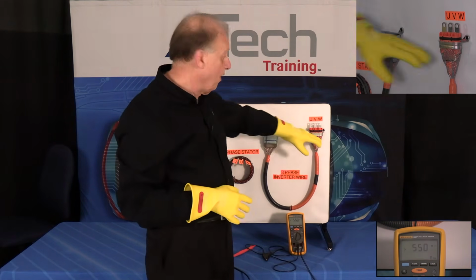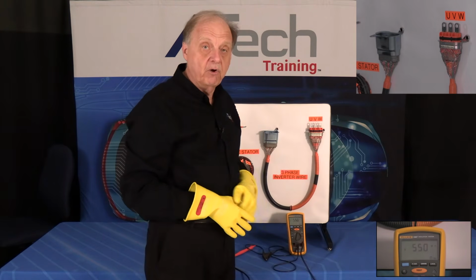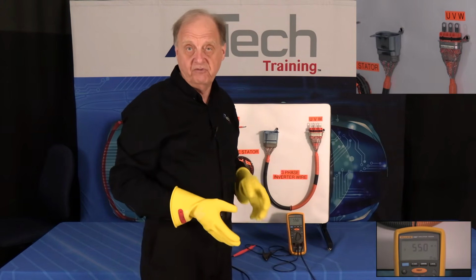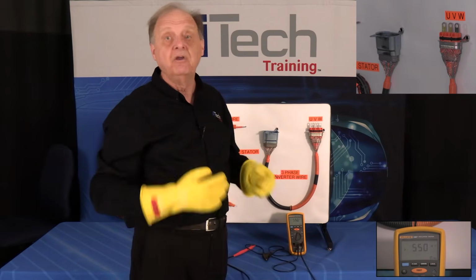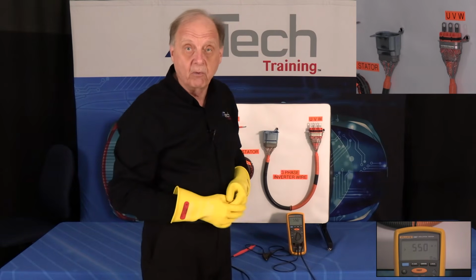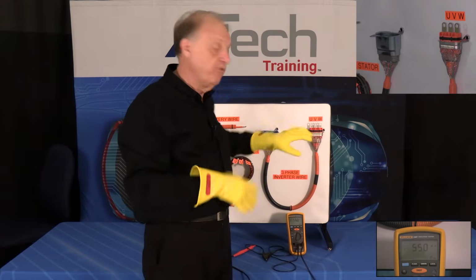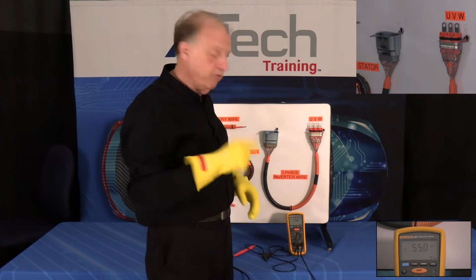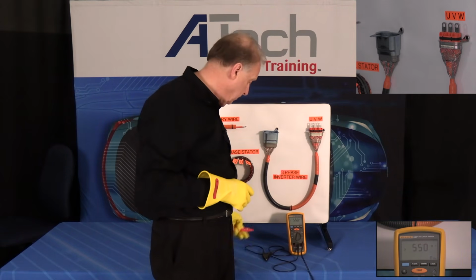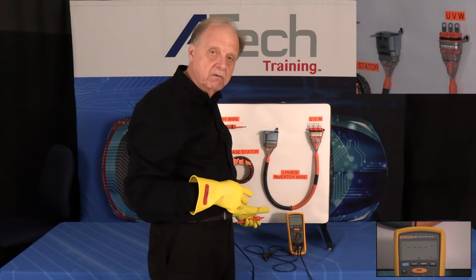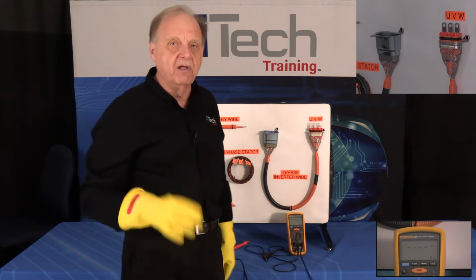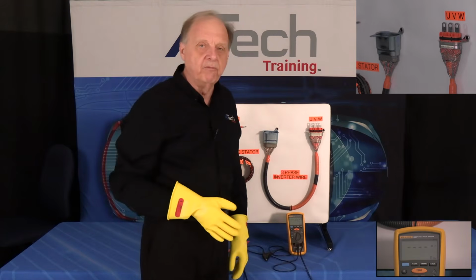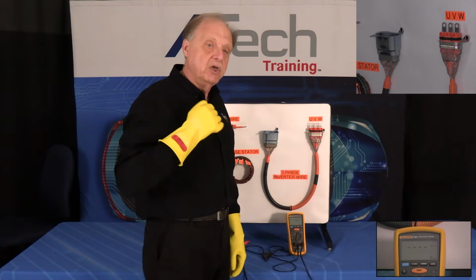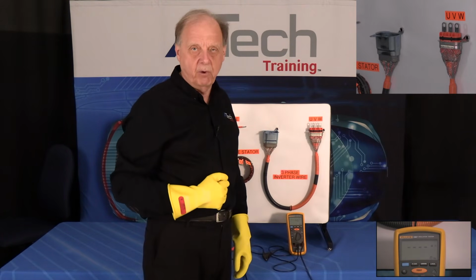Now, if there was a direct short here, the way this is inverted wire, there is a chance that you're going to short to the chassis on the vehicle or the body. So you don't want to have any of the stray voltage going around. You have to prevent it. So that's why we're doing this kind of testing. Notice my reading always stays there until I hit the button. Again, it always remembers until I hit the button, then it takes a reading. So that's what we use a meter. So that's what we're doing in this testing. You've got to do this to make sure everything's properly working.